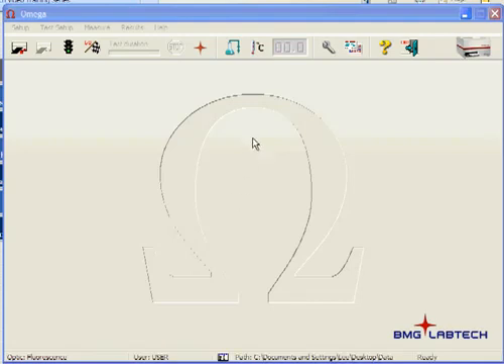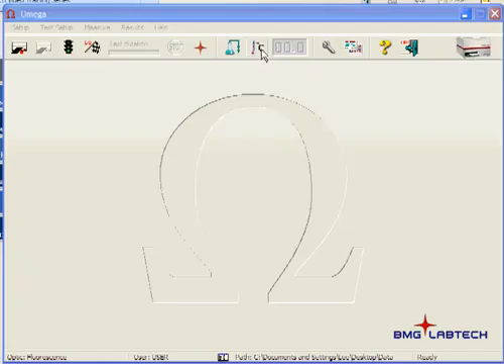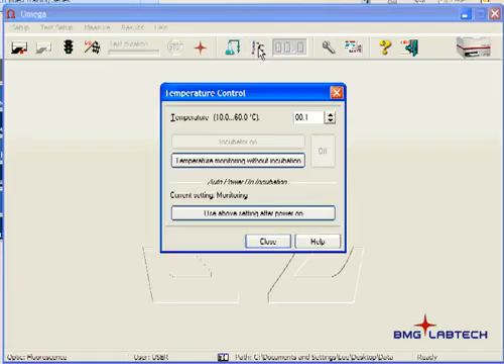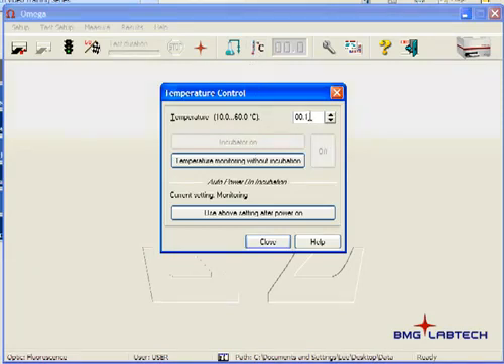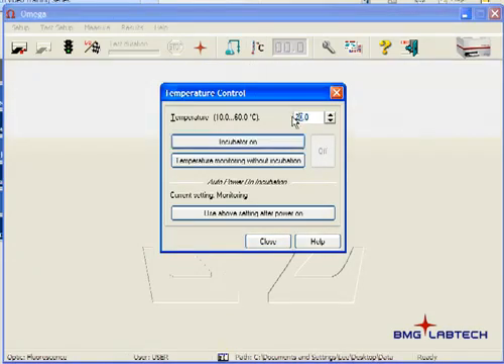The control icon for the incubator is up here at the top and the readout is here. If it's grayed out, that means it has not yet been enabled. To enable it, we just click on the icon and we have two options.